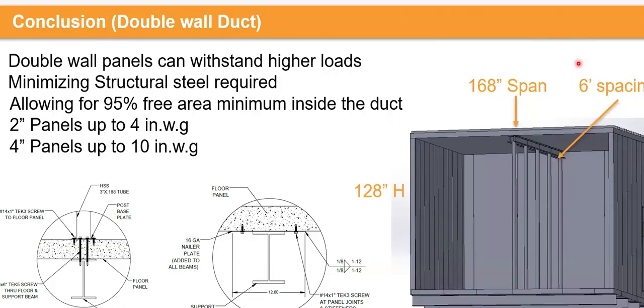spanning only 6 feet and running only along the center just to make sure that they are carrying the weight of this top panel. This would ensure that we are meeting both the positive and negative pressure ratings that these are designed for. And this is designed up to 10 inches of water gauge.